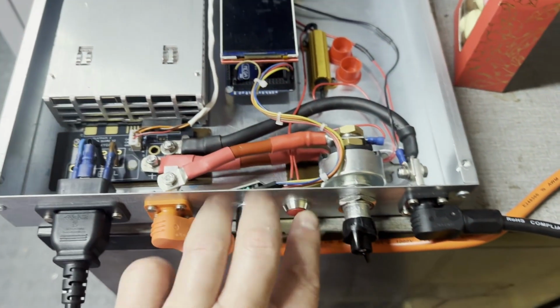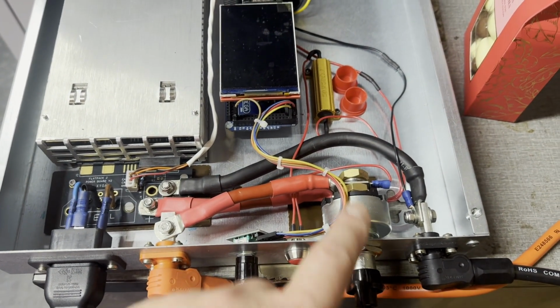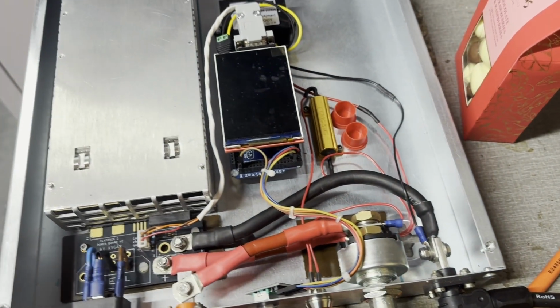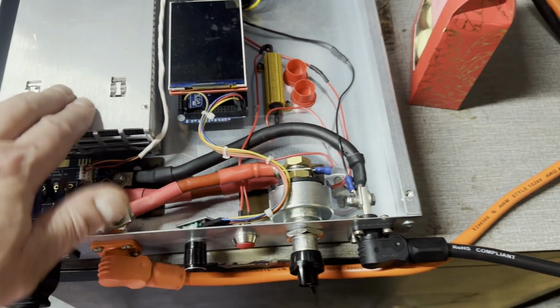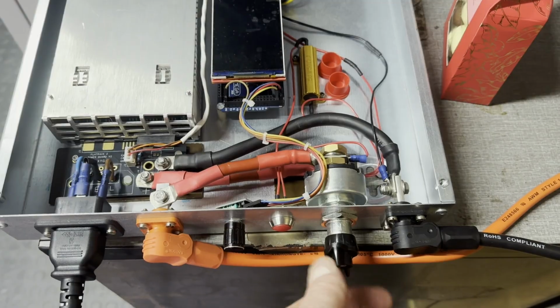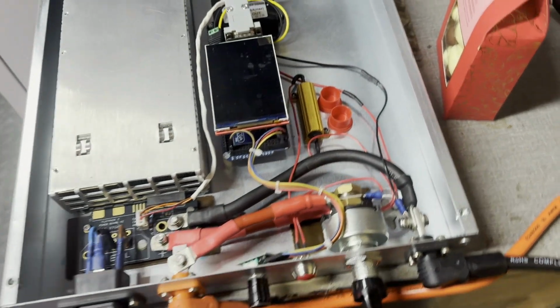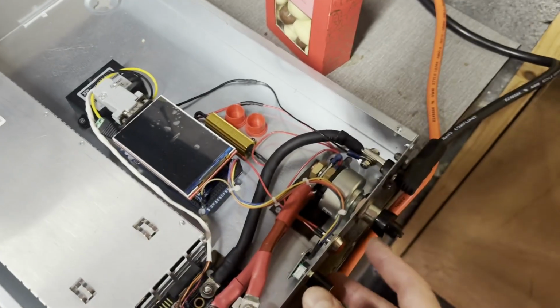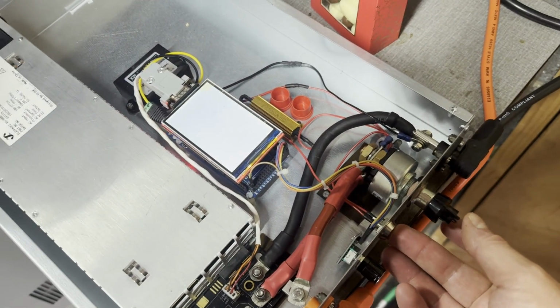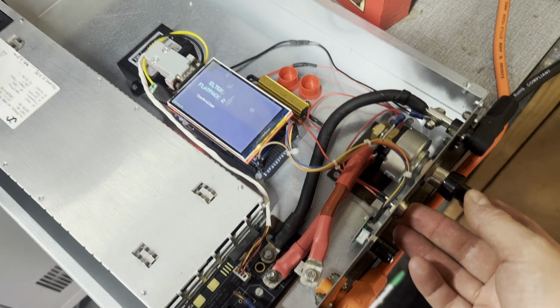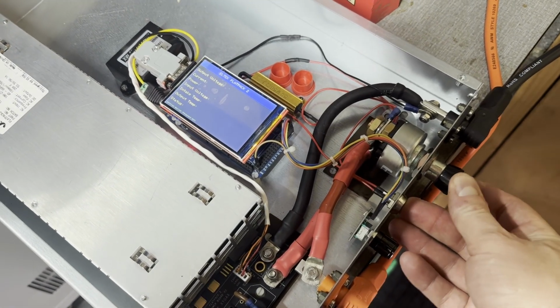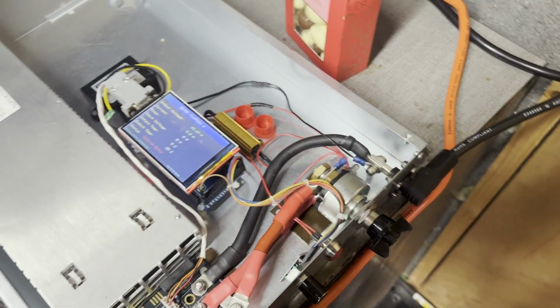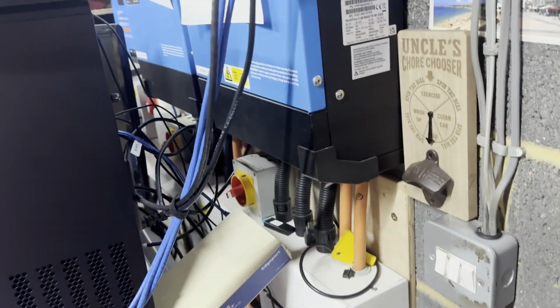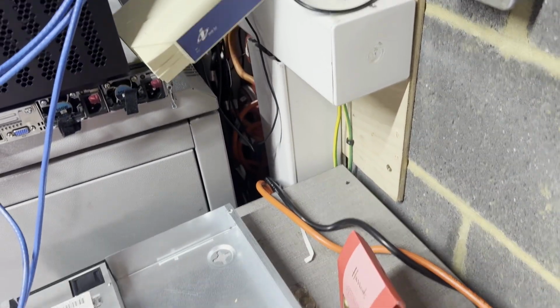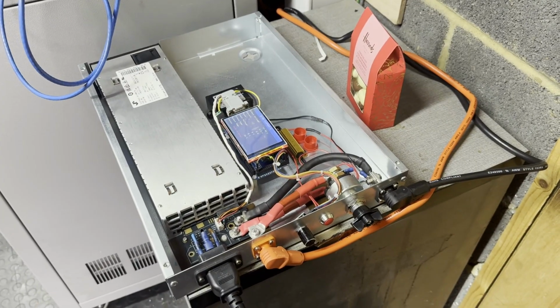It has a pre-charge button on there, so what I'm doing is just running it before you engage the thing, because there's capacitors in here, so you'll get a bit of an arc if you're trying to switch that on. It's just not good on all the capacitors. So you press the pre-charge button, which pre-charges the capacitor, and then I can turn the big battery on. So this is just plugged into my bus bars, so it effectively just looks like another battery.